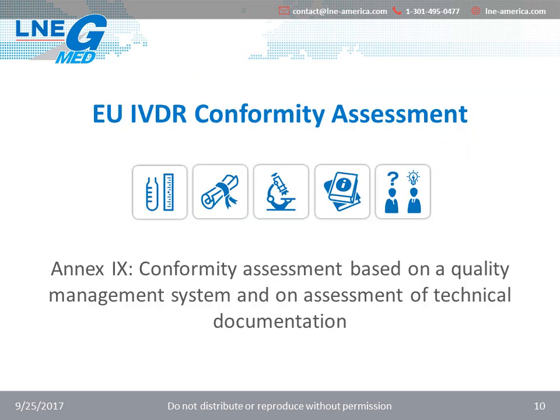So let's move now to the second section of this talk, which is to talk about the relation between the requirement of the regulation and the ISO 13485:2016 in the aspect of the conformity assessment, when that conformity assessment is based on Annex 9 and on the quality management system as well as the technical documentation. Here, I won't talk about the technical documentation, but I will just focus on the part of the quality management system.